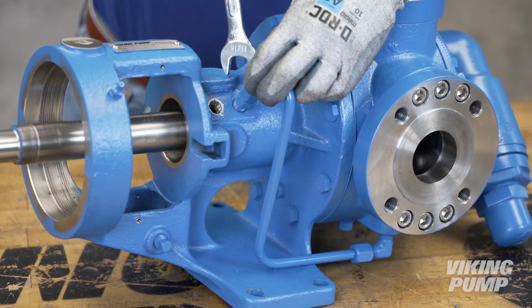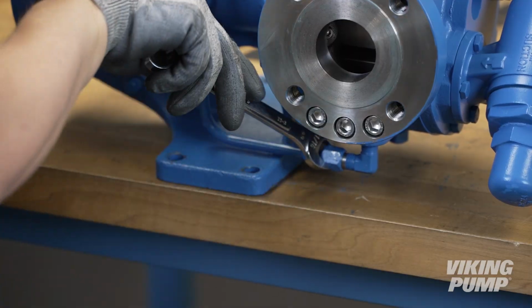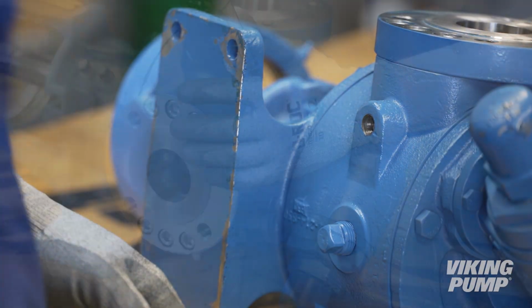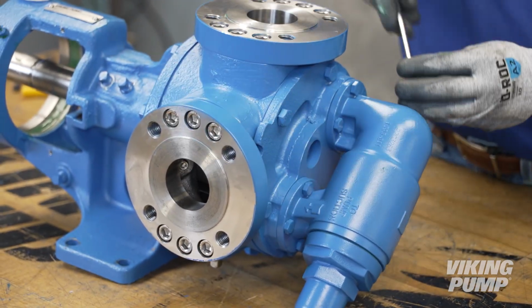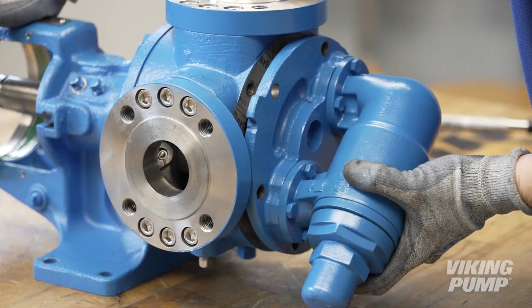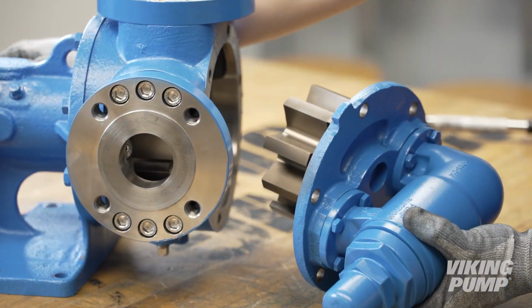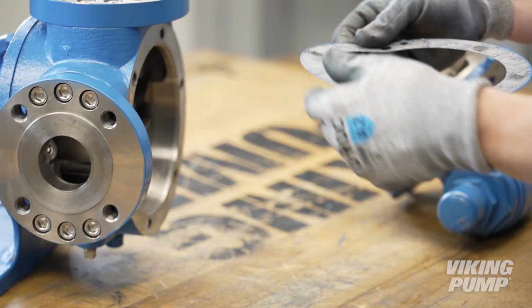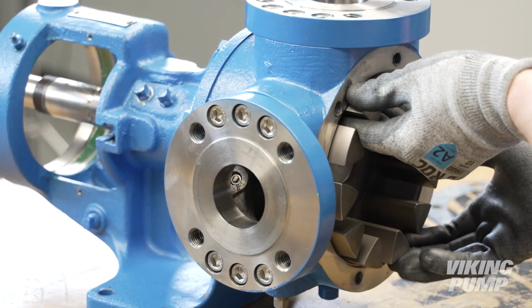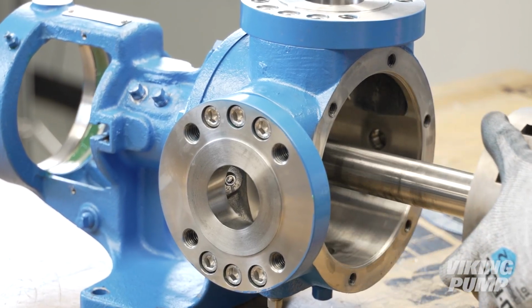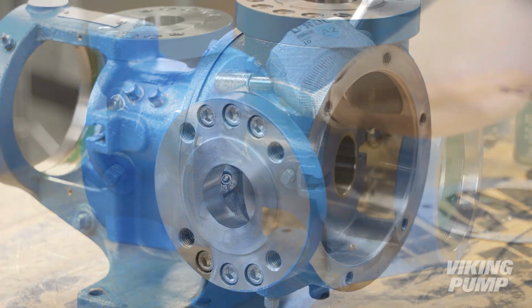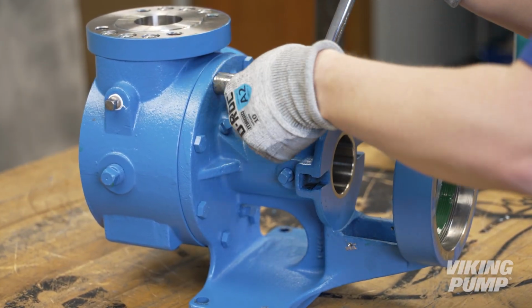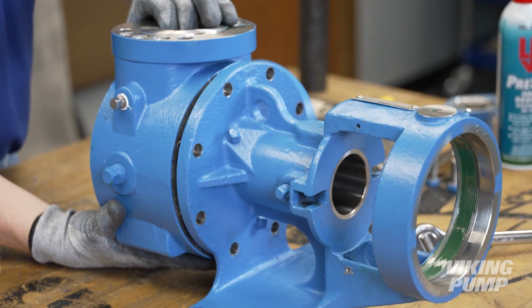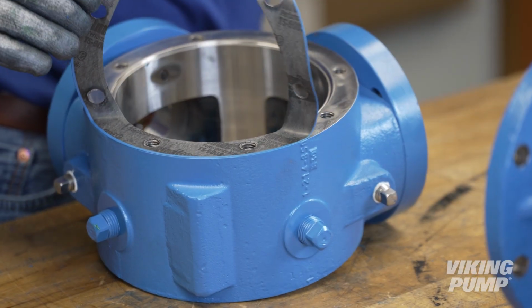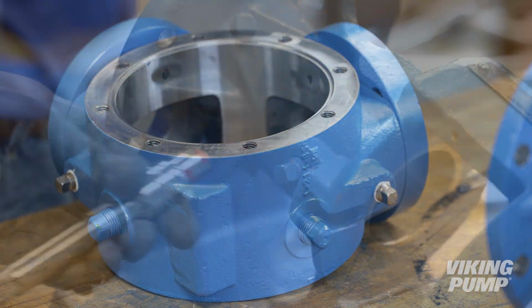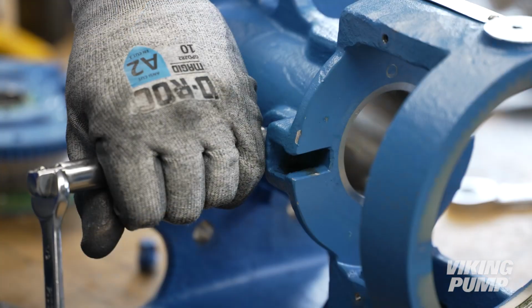Remove any suckback or flush lines and install plugs. Loosen and remove the head cap screws. Remove the head by tilting it backward to prevent the idler from falling off the idler pin. Remove and discard the head gasket. Remove the rotor shaft. A soft-headed hammer may be used to tap on the end of the shaft to aid with removal. Loosen and remove the casing cap screws and remove the casing. Remove and discard the bracket gasket. Remove the plug on the opposite side of the open seal access hole.